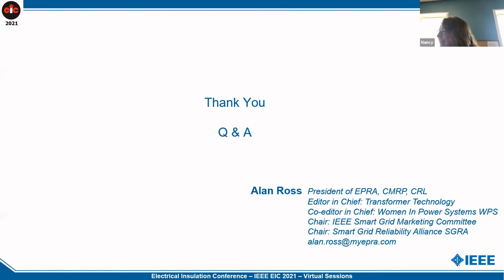I'm going to dig into, or ask you a bit more about that. 64% of the transformers have excessive moisture. You knocked my socks off with that data. Unacceptable moisture, 64%. Now, do you think that's partly because we're using transformers designed for 20 years that are operating at 38 years, or is it new designs, or just that number? I'm astonished that our assets are having that kind of red flag, or yellow flag, shall we say.